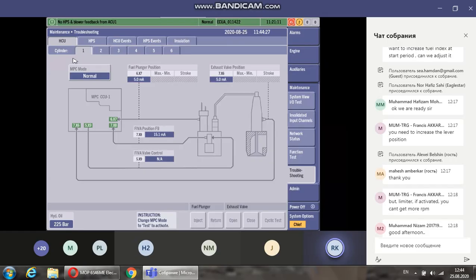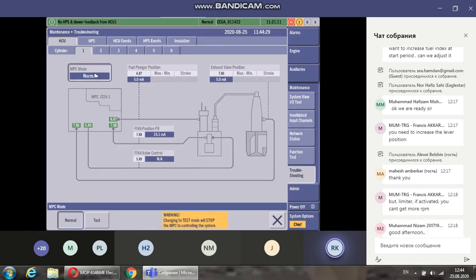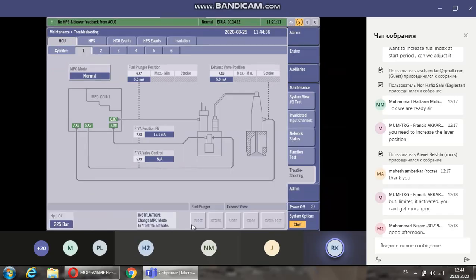For your number of cylinders, we can see that we have the option for the MPC mode. I can also take the MPC into test mode from this, and at the bottom you can see we can do an injection and a return. Using this one here, I will do a full injection. So the plunger inside the booster will go to the topmost point it can, and when you press return, it will return to the bottommost point.